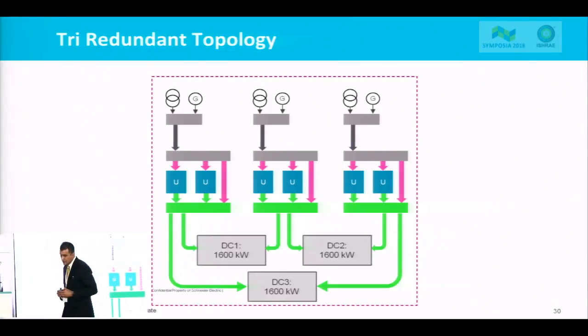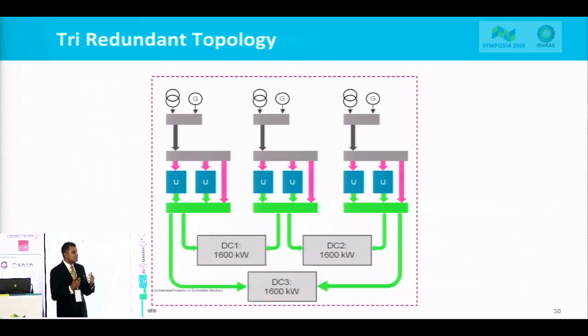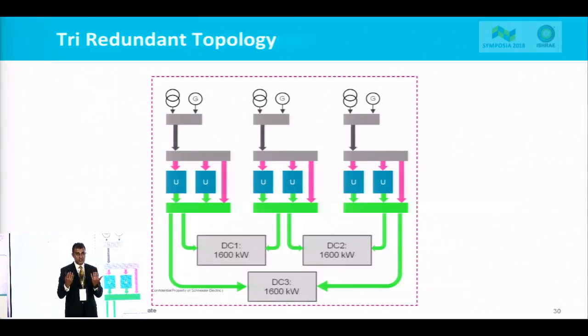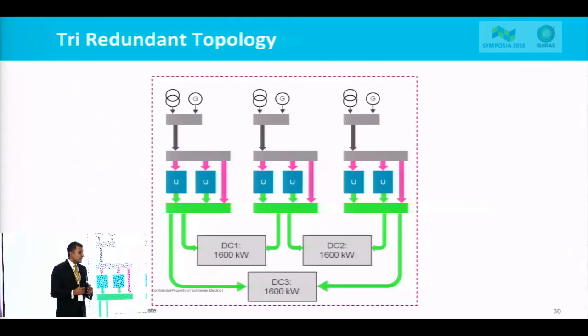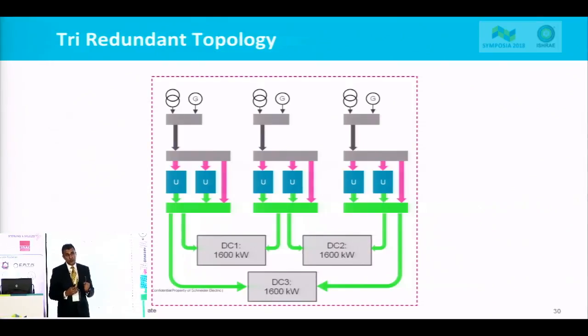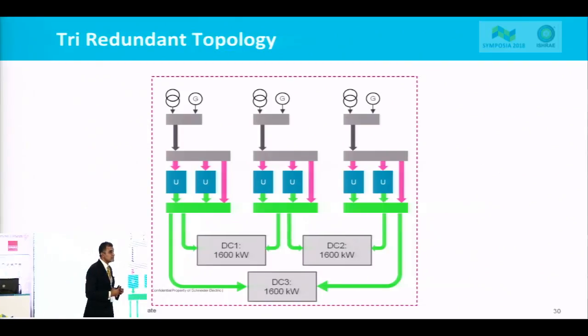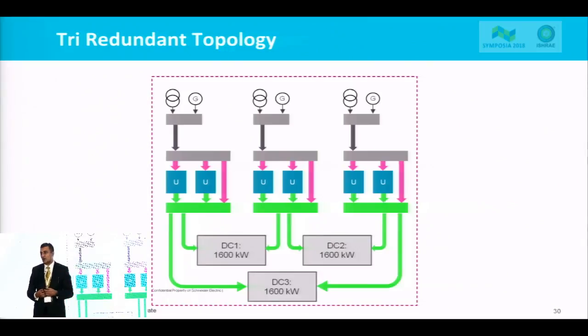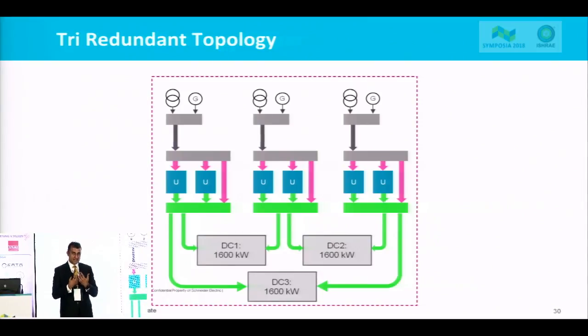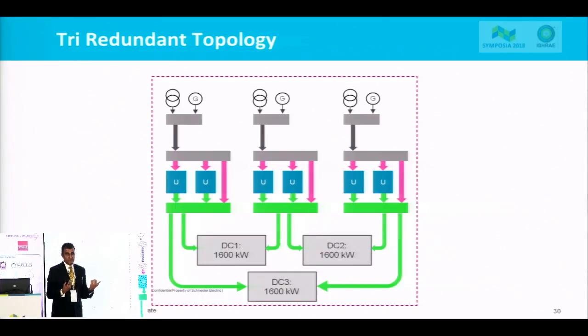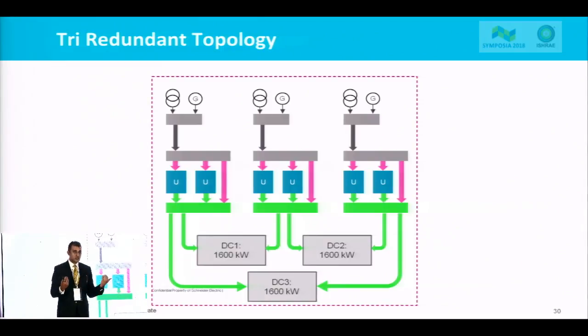Next, as I said, the core is the Uptime Institute tiering, and then there are subsets of that. This is a tri-redundant topology, and in this topology there are still two power feeds to the rack or to the IT load. The UPS capacity is 150% of the IT load. So now you've reduced the capex on the UPS spend. In the tri-redundant topology, it also depends on the requirements of a project and also a country. In some instances and in some countries, you have certain capacities of transformers or UPSs or a product line that is cheaper for a certain size, and that's one of the ideas behind using a tri-redundant topology to reduce the capex. But it still offers the resilience of a 2N topology.